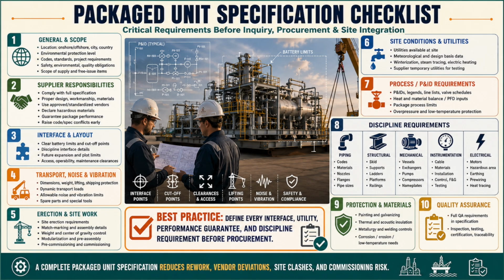Thermal insulation must identify whether its purpose is heat conservation, cold conservation, condensation control, freeze protection, or personnel protection. When insulation is essential to the process performance guarantee, the supplier should remain responsible for its design and installation. Otherwise, the vendor may guarantee performance, assuming insulation that another contractor installs incorrectly. For fired equipment, include refractory requirements. Where insulation is supplied loose for site installation, identify each item and require detailed installation instructions, material schedules, and fastening details.